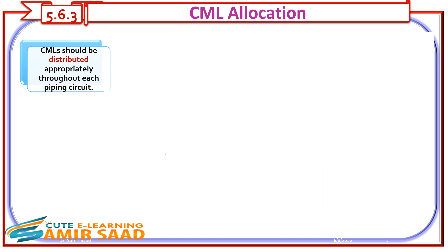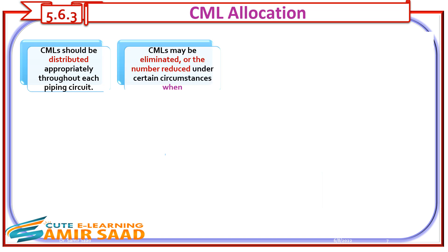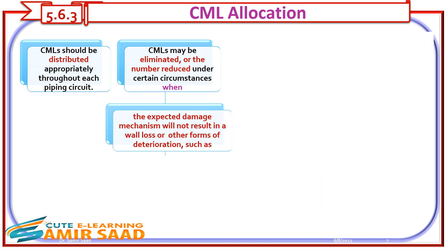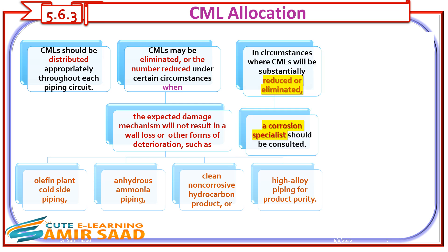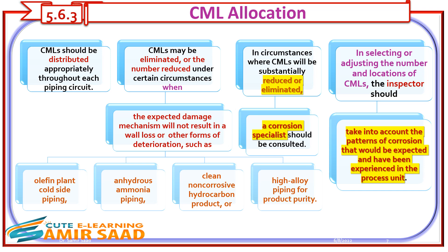CMLs should be distributed appropriately throughout each piping circuit. CMLs may be eliminated or the number reduced under certain circumstances when the expected damage mechanism will not result in wall loss or other forms of deterioration — such as olefin plant cold side piping, anhydrous ammonia piping, clean non-corrosive hydrocarbon product, or high-alloy piping for product purity. In circumstances where CMLs will be substantially reduced or eliminated, a corrosion specialist should be consulted. In selecting or adjusting the number and locations of CMLs, the inspector should take into account the patterns of corrosion that would be expected and have been experienced in the process unit.